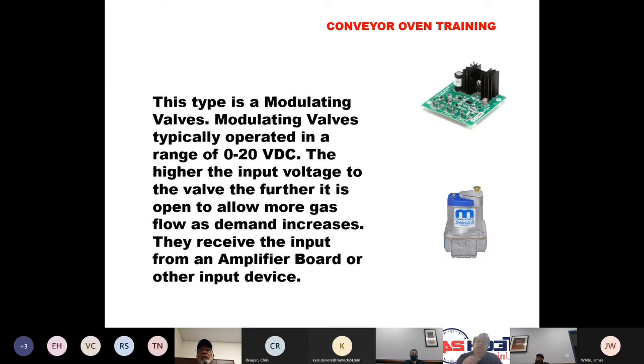This valve is called a modulating valve. Modulating valves typically operate in the range of 0 to 20 volts DC. The higher the input voltage to the valve, the further it is open to allow more gas flow. As demand increases, they receive the input from an amplifier board or other temperature control device. So basically, this valve is always opening and closing. When there's more of a demand for heat, it will open more. As that heat demand decreases, it will close more.